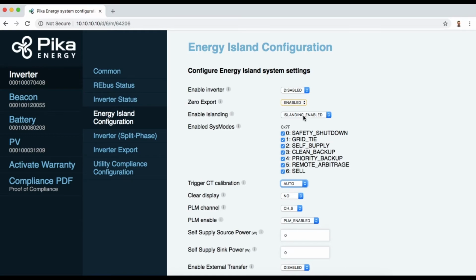Because this customer has a backup loads panel, I'm going to select Islanding Enabled. If this customer had an inverter installed and was just net metering, then we would likely choose Islanding Disabled. But in most cases, and in the case of this customer, we're going to select Islanding Enabled. If you were required to lock customers out of any certain system modes, this is where you would do it.